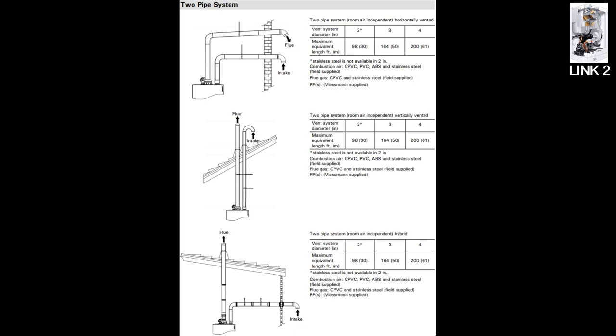The flue pipe should be pitched back towards the boiler so that the gas condenses inside of the pipe, it will flow back into the boiler. The intake pipe should be cleaned to make sure that there is no debris inside of the pipe. Otherwise, it could be sucked into the burner assembly and possibly damage it.